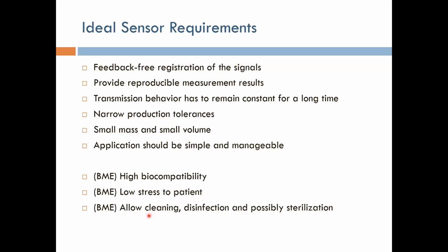Another very important characteristic is that the sensor should allow cleaning, disinfection, and possibly sterilization. Imagine a medical device using a sensor on a patient with an infectious disease. You cannot use it directly on another patient. You have to be able to clean it, and if something spills on it, you have to be able to disinfect it, and ideally sterilize it.